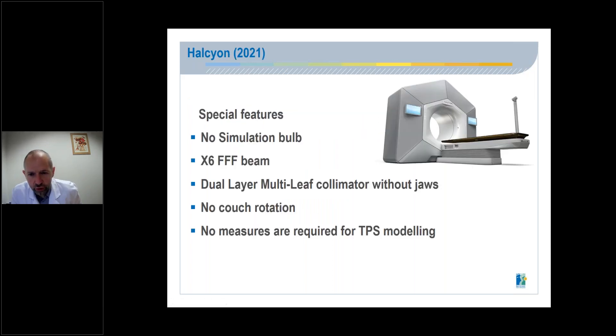What are the special features of Halcyon? There is no simulation bulb. Beam is an FFF. Collimator is a dual layer multi-leaf without jaw. There is no couch rotation. No measures are required for TPS modeling. The system is installed with golden data inserted into the beam configuration.